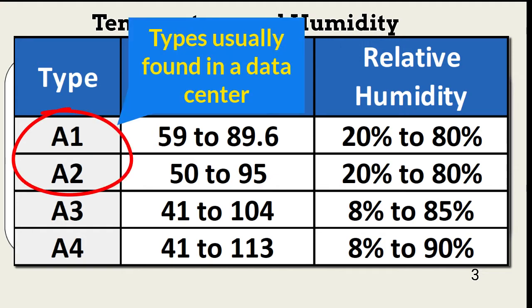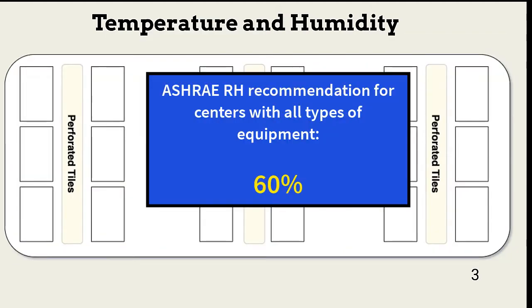In addition to cooling, data center humidity must also be controlled. Humidity levels are also determined by the types of equipment present. ASHRAE recommends a relative humidity of about 60% to address all types of equipment.